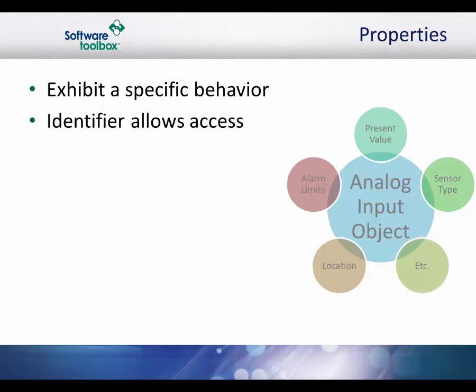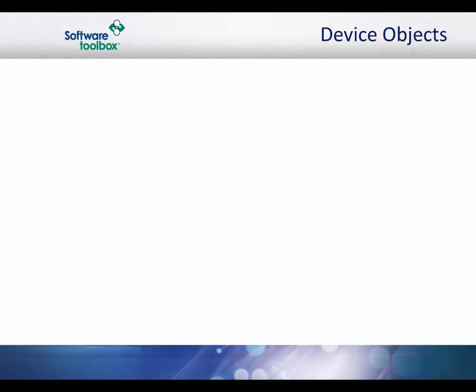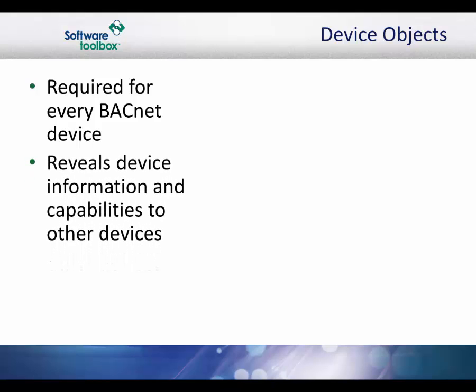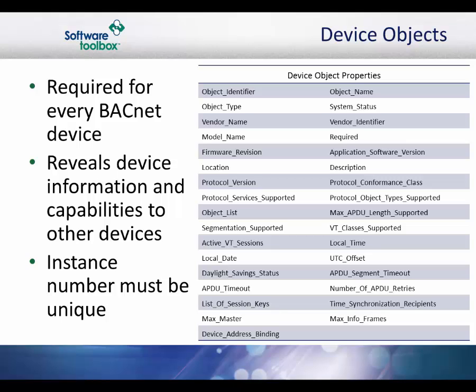Here is a list of the defined properties of the analog input object. BACnet requires one device object to be present in every BACnet device. The device object makes information about the device and its capabilities available to other devices on the network. Before one BACnet device starts control-related communications with another, it needs to obtain some of the information presented by the other device's device object. Here are some example properties of a device object. Unlike other objects, the device object's instance number must be unique across the entire BACnet network because it is used uniquely to identify the BACnet devices.